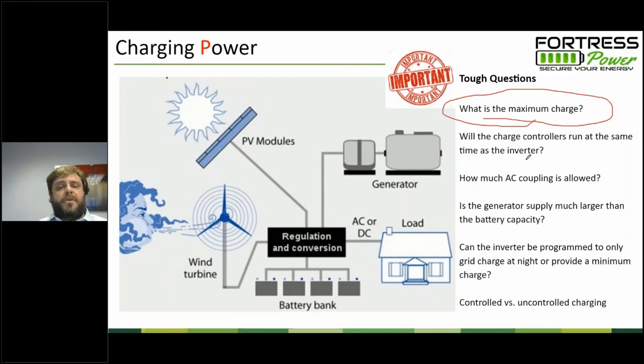So that's where you might want to have the grid charge come on only at very low states of discharge. In an off-grid setting, you don't want the generator to click on every single day. You want enough storage to get you through so that the sun can come up and charge it, reducing your generator consumption. But the concern is when you're grid tied, if you make it all the way to 4 or 5 a.m. and then the grid says, okay, your battery's depleted and I need to turn on and charge, and you start charging with your grid side, and then the sun comes up and your charge controllers go on full blast, could that result in an overcharge situation?